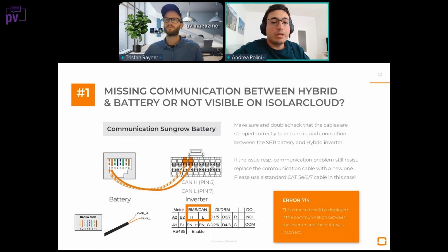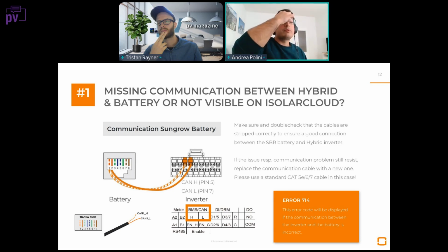If this issue persists, even though you have double or triple checked the connection between hybrid and battery, we recommend that you take another cable, just a standard Ethernet cable from your home or from whatever installation is there. Just take a standard cable and do the same connection: connect it on the battery side to the patch connector, and then on the inverter connector the same way. If this is still not working after that, then you can definitely contact Sungrow service, and be careful to also provide us with pictures of both sides of the connection, and then probably also a single line diagram of how the connection was made.